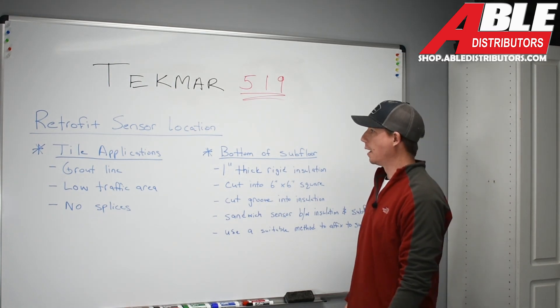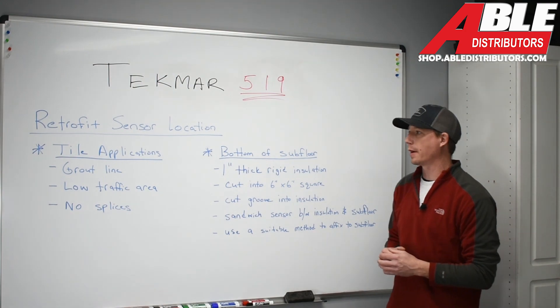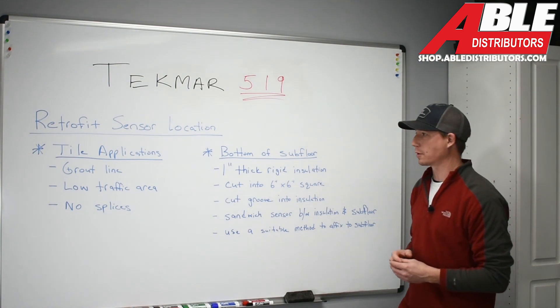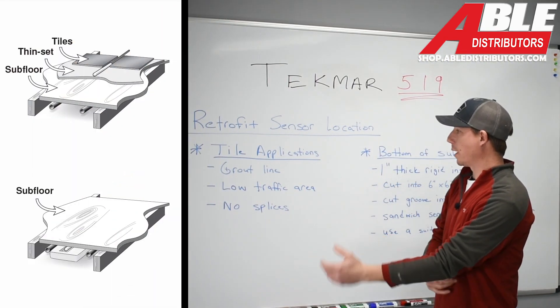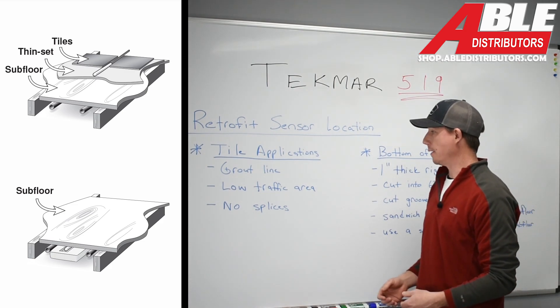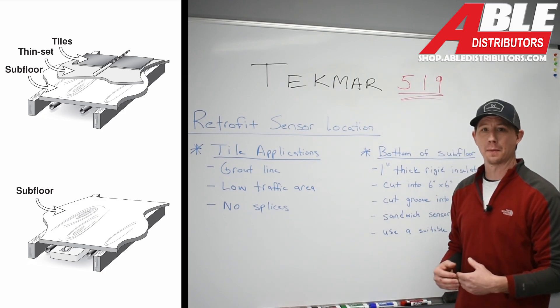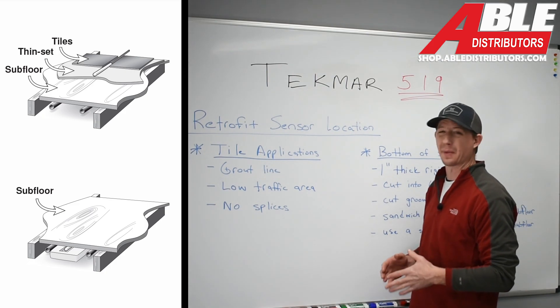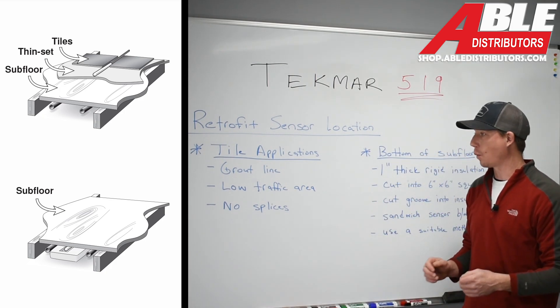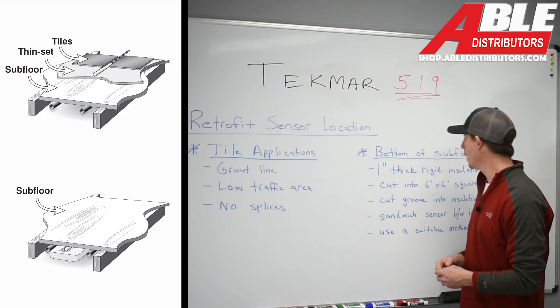Back at the tekmar 519 retrofit sensor locations — retrofit meaning we currently have a radiant floor installed with a tekmar 519 control, and our sensor is going bad, and the prior contractor didn't give us any ability to replace that sensor. For tile applications, we can chisel out that grout line and retrofit that sensor into a new location. We want to put that sensor in a low-traffic area so it doesn't disrupt the grout. We also need to make sure there are no splices in the floor — the wire should run directly to the control, or if spliced, make sure it's on a wall out of reach of nails or screws.